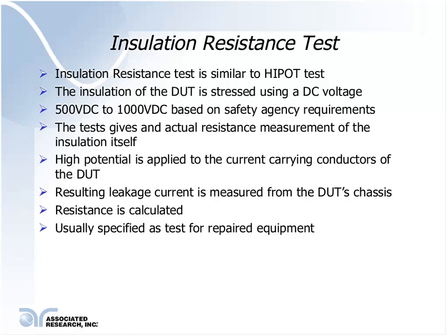Similar to the Hipot test, the insulation resistance test is run by shorting the mains inputs of a device under test.